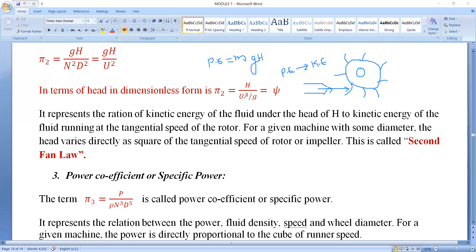The denominator term u²/g represents the kinetic energy of the fluid running along with the runner — that is, the fluid running at the tangential speed of the rotor. So psi is H divided by u²/g. For a given machine with some diameter, the head varies directly with the square of the tangential speed of the rotor or impeller. This is called the second fan law.